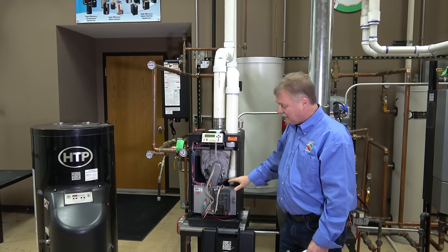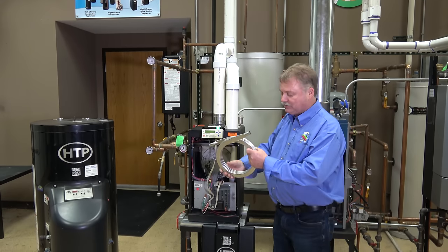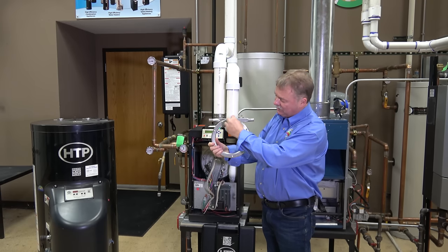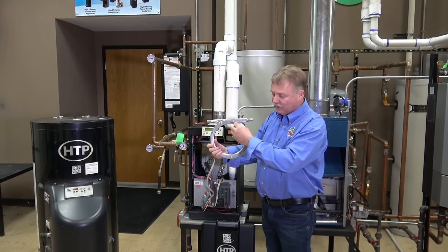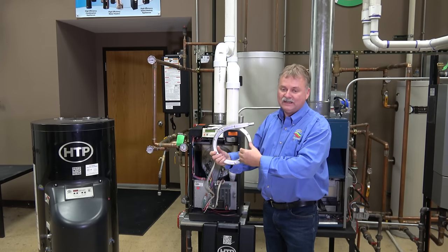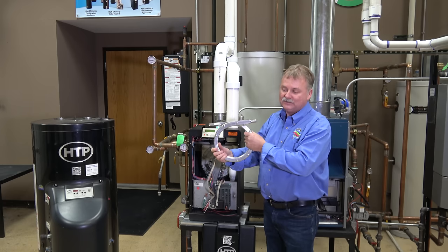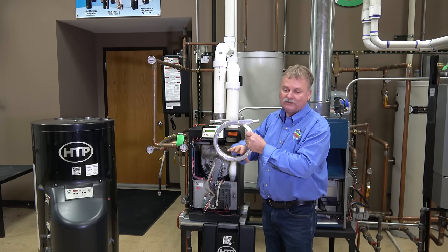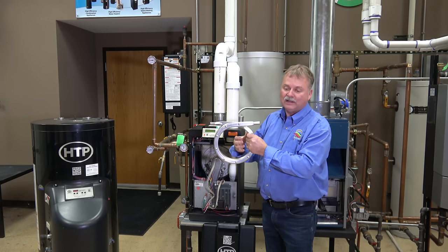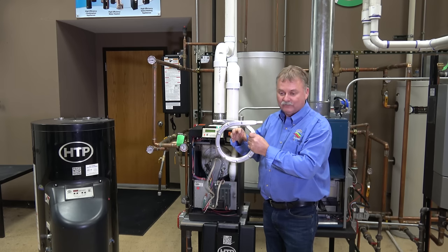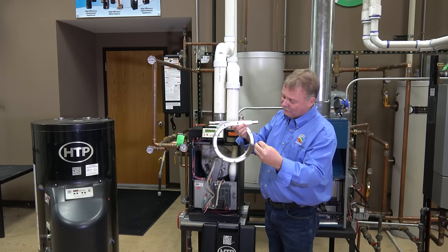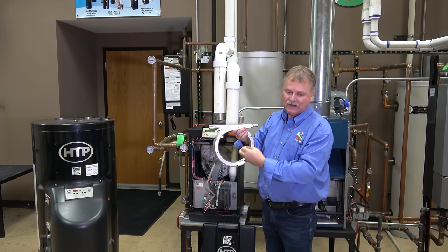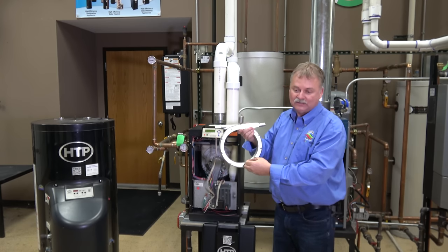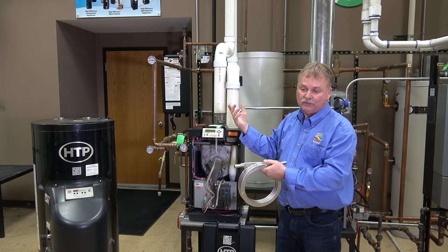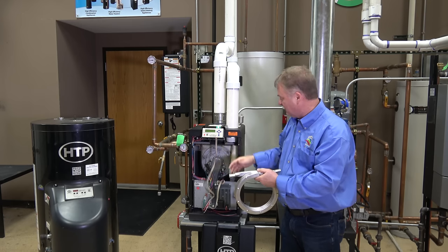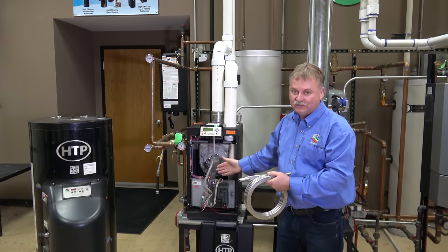The thing about a condensing boiler is that as we're shooting this flame through this heat exchanger, which is filled with water, we're trying to get that temperature so low that we condense the flue gases. What that means is the flue gases themselves turn back to water. By doing that, we absorb a lot more heat out of that fire. In other words, all those dollars that we're throwing into this heat exchanger, we're trying to extract every dollar we can to put into the system to go out and heat all of our terminal devices, our radiant floor and whatever.